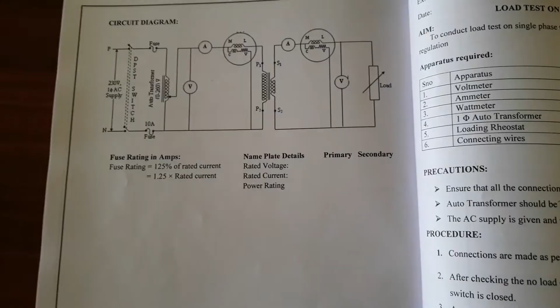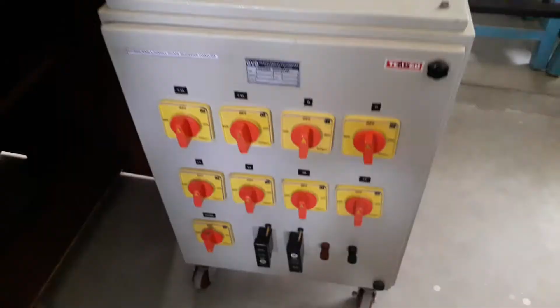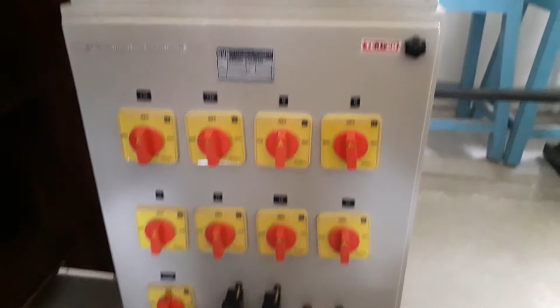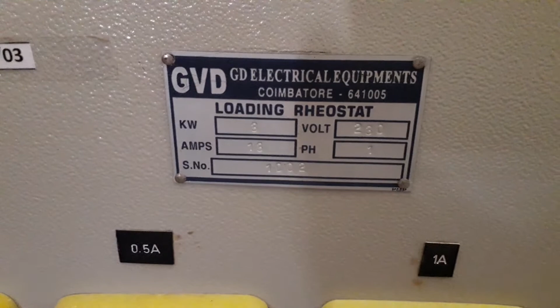See here, this is the single phase resistive load. This is the nameplate detail you must understand: the kilowatts is some 3, the voltage is 230, and the amperes you can consume is up to 13 amperes, and it is single phase.